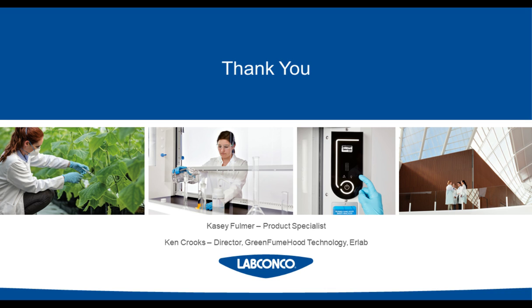Yeah, I'll jump in. Thanks, Kasey. Exactly right. And so that's the modified testing in the field, because SF6 or NOx, the typical tracer gas, is now in place, even though ASHRAE is changing that. The SF6 NOx, they will go through the filter and invalidate the test results. So we've got that modified test procedure for in the field. At the factory, the fume hood manufacturers do a full and complete 110 test. They attach a duct to the top of it where the filters are and exhaust that tracer gas so that it doesn't invalidate the results.